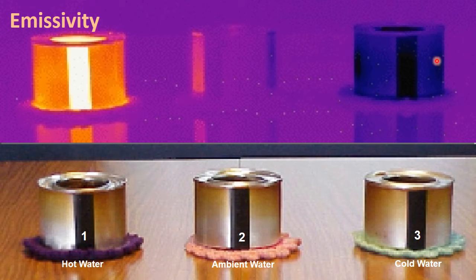If I look at the colder can which has cold water, the actual tape looks cooler than the actual body of the can. That's because the can has been apparently warmed by the reflection of the background temperature which is warmer than the actual fluid that's in the can. So you start to see that it becomes imperative that you understand that what you're seeing in the camera and the emissivity of the materials and the way it's being affected by the reflection of background temperatures, you can make a really bad call if you don't know what you're doing.